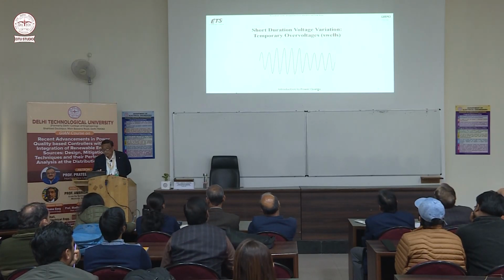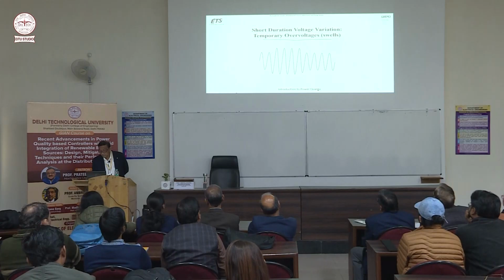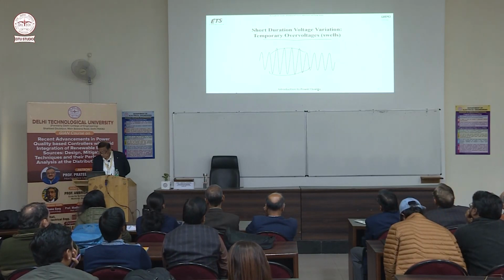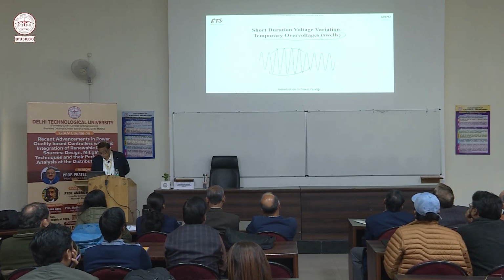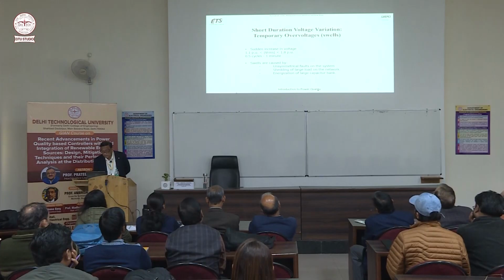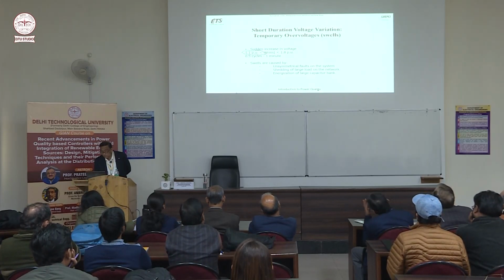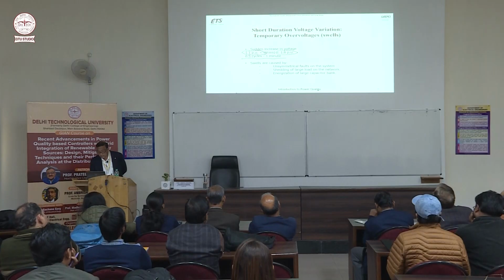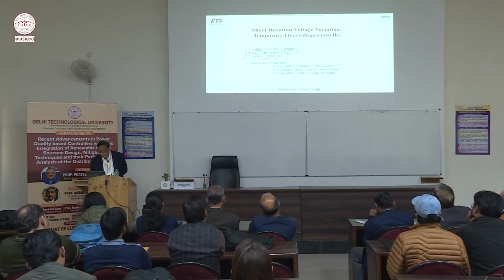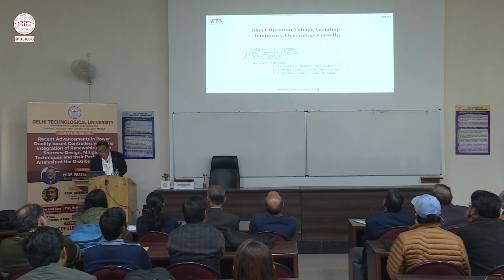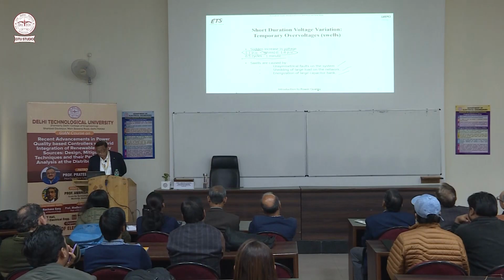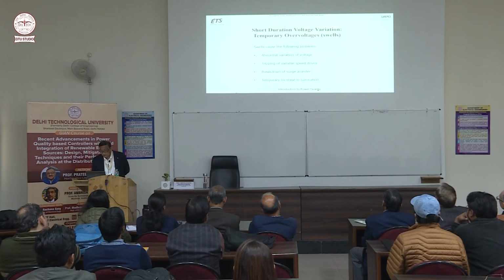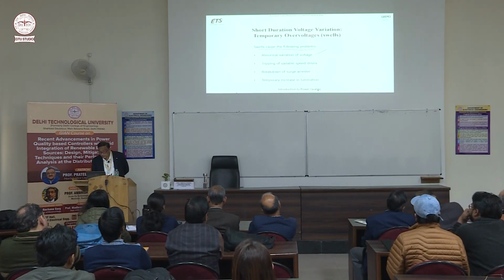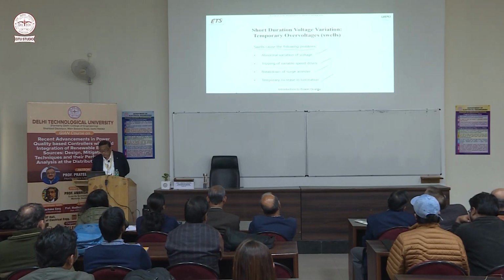Short duration voltage variation, temporary over voltages. See, you have over voltages for short duration. Voltage swell, we call it swell. Sudden increase in voltage between 1.1 pu to 1.8 pu, between half cycle and 1 minute. So swells are caused by unsymmetrical faults on the system, shedding of large load, energization of large capacitor bank. So these are the causes of the swell. Swells cause the following problems: abnormal variation of voltage, tripping of variable speed drives, breakdown of surge arrestor, temporary increase in illumination.